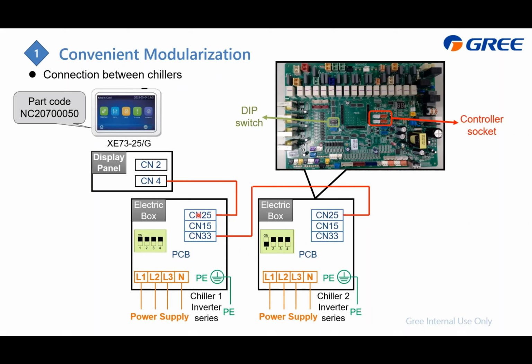Generally, if this chiller is connected to the controller, this one is the master, which means this switch should be all set to bit 0, just like this. For the other one, you just need to change it to a different setting, and it's okay. If you're going to connect more than 2 chillers, connect from this CN33 to the next CN25. The maximum we can connect is up to 16 chillers.